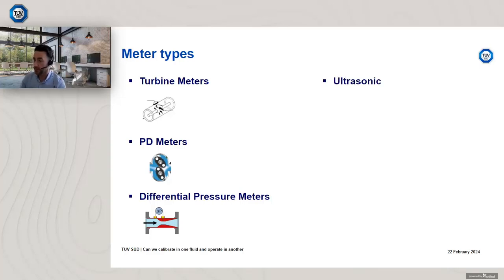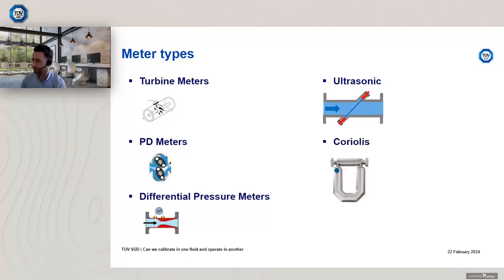Ultrasonic meters, again, similar to the turbine devices and PD meters that I mentioned, are fluid sensitive, and the design is sensitive to which fluid you're using. So a gas ultrasonic can't be applied to liquid use, and a liquid ultrasonic meter can't be used with gas, due to the different transducer frequencies in design.